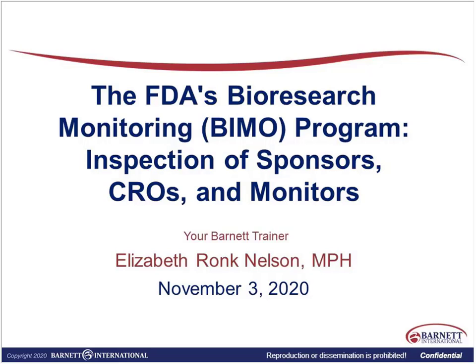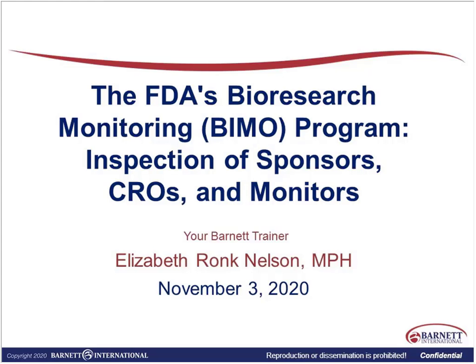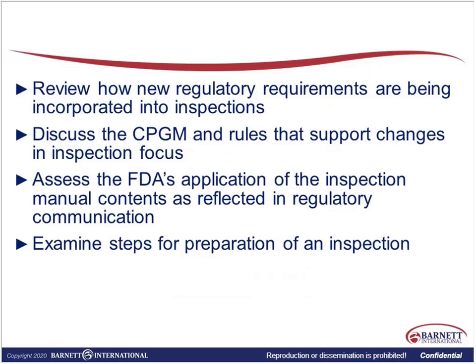They use a document called the FDA's Compliance Program Guidance Manual, and we're going to talk specifically about 7348.810. We certainly have that as a handout here. Really, this is how the FDA conducts those inspections — it's the SOP for how they conduct those inspections. It's very helpful to understand what they're looking for and make sure that our quality subsystems align with that.